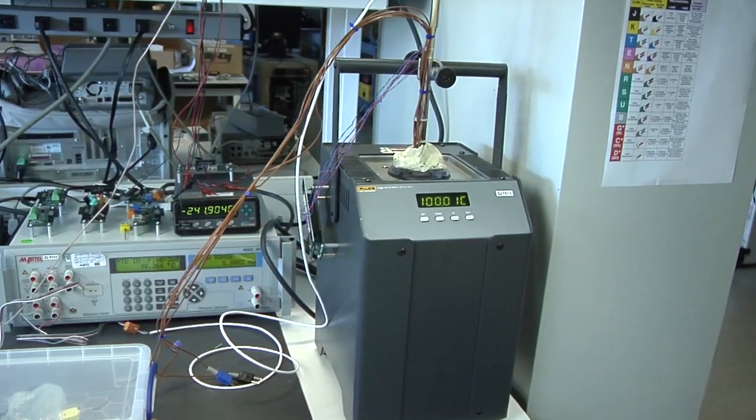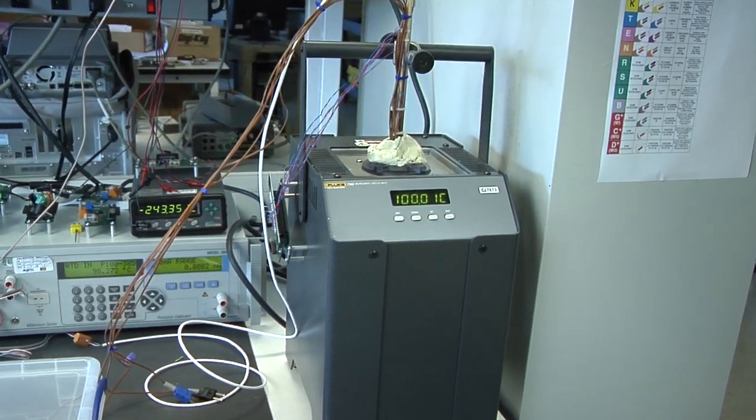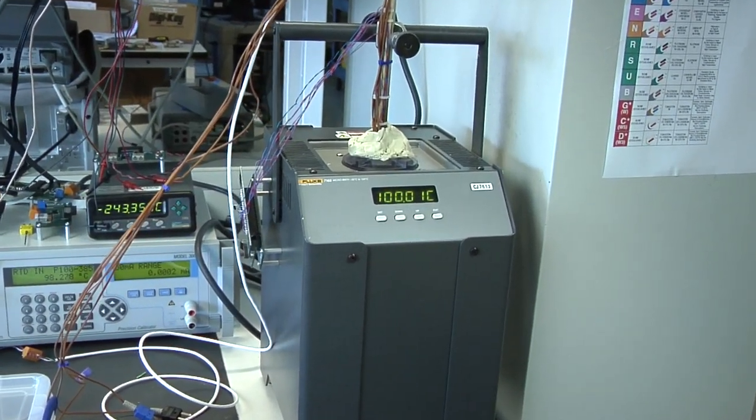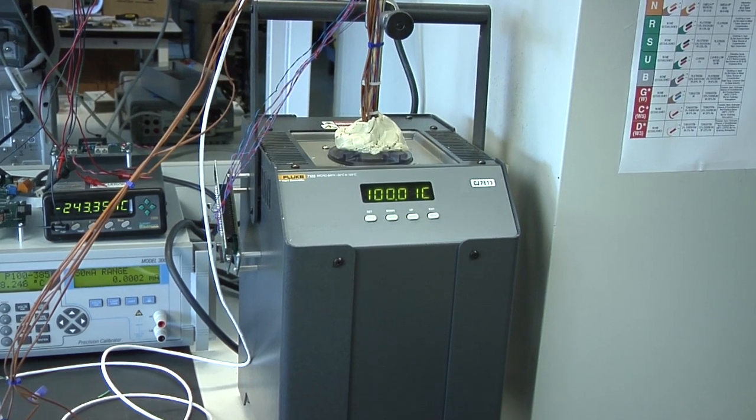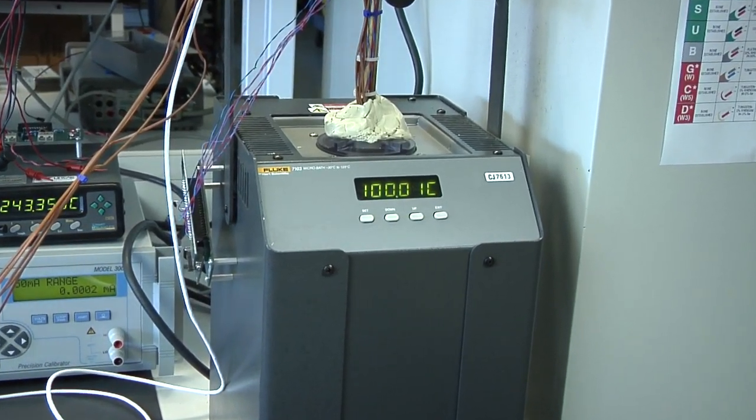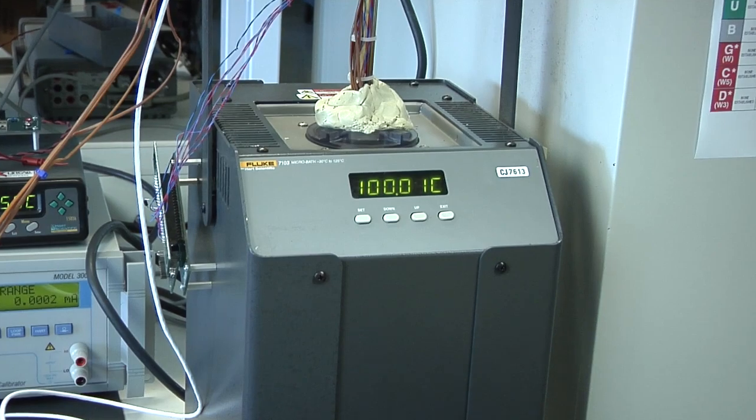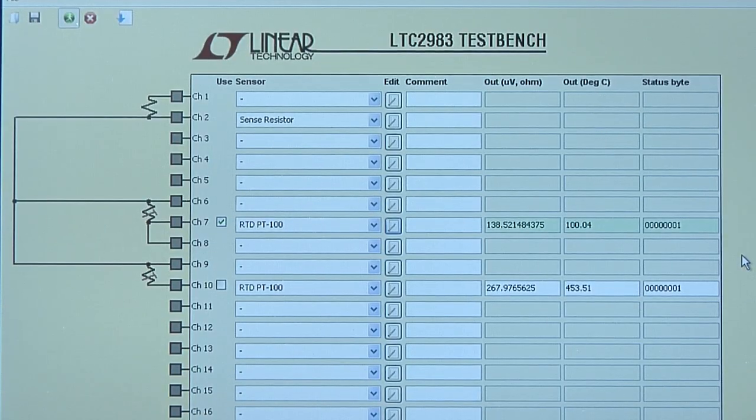An accurate method to measure temperature with a real sensor is a temperature controlled oil bath. In this case, a 4 wire PT100 RTD is inserted in an oil bath set to 100 degrees C.